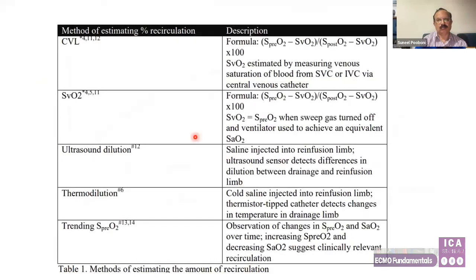There are various methods to estimate the percent of recirculation. The formula would be pre-O2 minus venous O2, divided by post-O2 minus venous O2, into 100. You can use the central venous method, where you can draw blood from the superior vena cava and inferior vena cava, or you can use the formula where SvO2 is equal to SpreO2 when you turn off the gas and ventilator used to achieve an equivalent SaO2. Another is thermodilution, where you inject cold saline into the reinfusion limb and a thermistor tip catheter detects changes in temperature in the drainage limb. Or the best method would be to serially check the oxygenation in the pre-oxygenator flow, and a serial increase would suggest there is definitely clinically relevant recirculation.